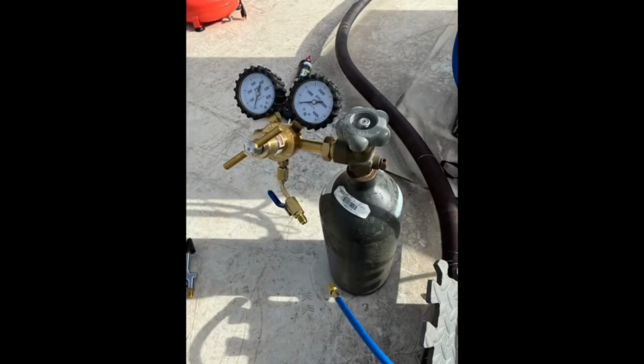So back up on the roof at the condensing unit, I did a nitrogen test. It held for 15 minutes, didn't leak down. So then I went ahead and released the nitrogen and hooked up my vacuum pump, pulled a vacuum. You want to get it at or below 500 microns. If it passes that decay test, then you can go ahead and open the service valves and release the refrigerant charge out of the condensing unit into the line set and the evaporator coil.